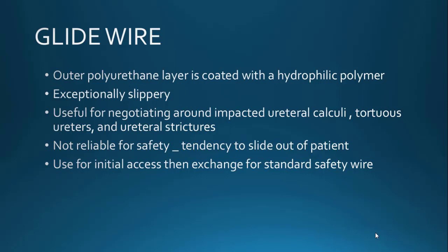The other guide wire is stiffer and tougher. The Glidewire is more slippery, while the other one is stiff and hard, and it can cause more damage than the Glidewire. First we usually try the Glidewire, and then we go for the stiffer guide wire.